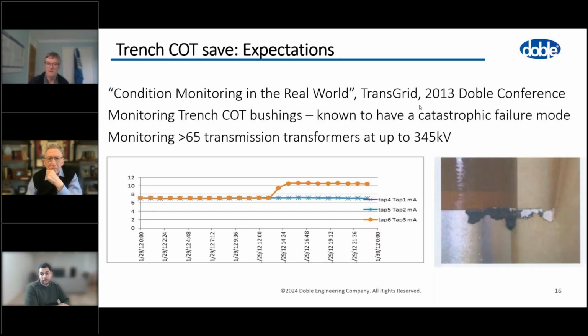But that transformer has a 50% rise in the leakage current magnitude over 2 hours. This is not the point at which we start to have diagnostic discussions. This was Transgrid, and these are the guys who had a policy that said, when this comes in, top level alert, take it out within 2 minutes. And the alert came in on the right-hand side, and that's what they did. At that point, you've got a sustained degradation. It fits in with the failure mode, and the forensics on the right showed the tear in the insulation as a result of the manufacturing process. So 2 similar cases on bushings, but we always go for what contextual data do we have available. Not always easy to find.